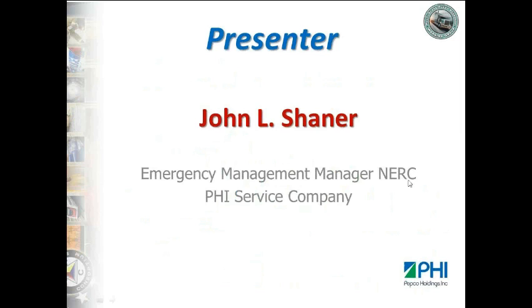I'm going to go through this real quick. Basically, we talked about the difference in priorities when you change from a system issue into a more transmission system restoration event. And basically what this slide is showing you is that you have units that are capable of starting other generating units up, a black start unit. Let's pretend that's the one down in the lower left-hand corner. You use the transmission facility, the bulk power system, to start up another unit that is required. That unit has to crank, and it has what they call ramping rates, where they have to have so much load per minute to ramp up into a stable mode. Distribution load is used at that point to stabilize the power station. Then that power station is used to start other power stations across the system.